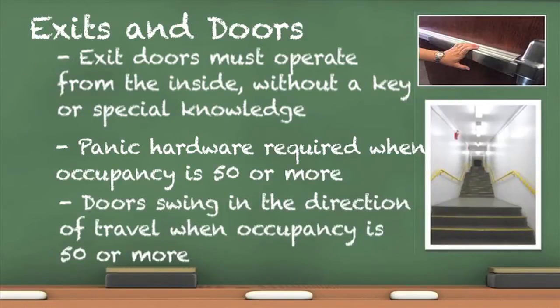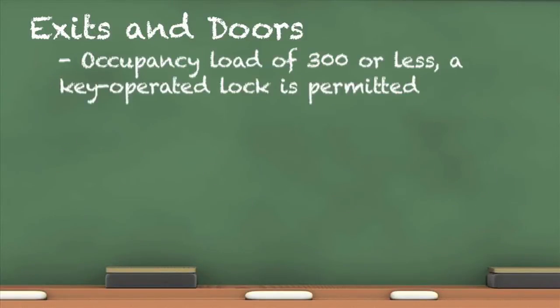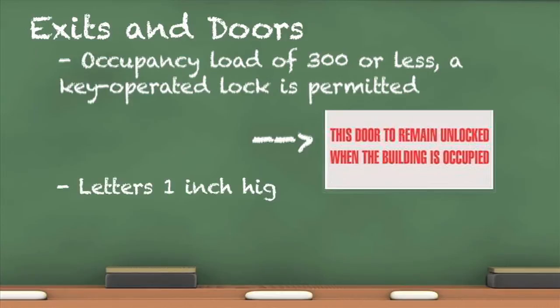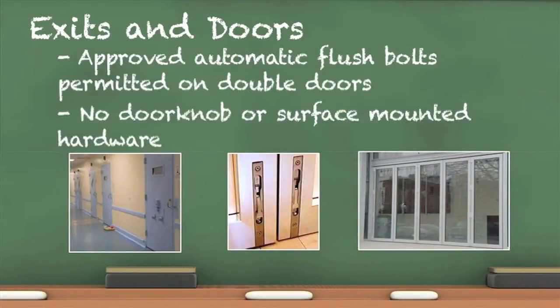There should be no obstructions of any kind. Specific guidelines govern the use of locks and latches in A occupancies. In buildings where the occupant load is 300 people or less, a lock is permitted on the main exterior door. A sign is required above or near the door stating this door to remain unlocked when building is occupied, in letters at least one inch high with a contrasting background. When egress doors are used in pairs, such as double doors, automatic flush bolts are permitted; however, door knobs or other surface-mounted hardware are prohibited.